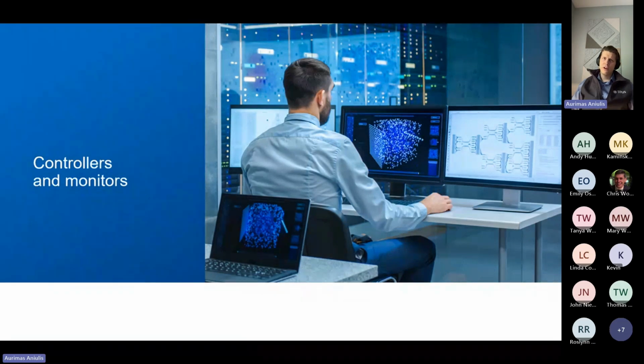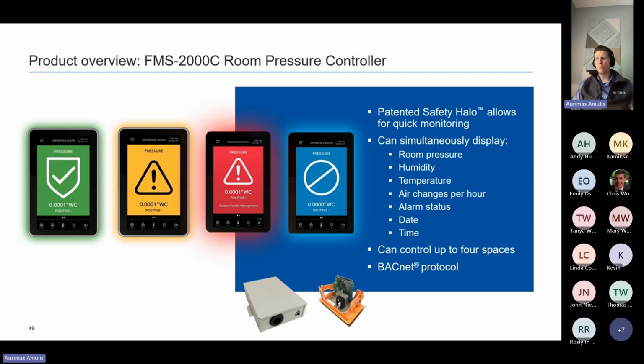So that's it for the air valves. Now we're going to get into controllers and monitors. These are kind of like your brains and your eyes and ears in a space. And the first one is the FMS 2000C room pressure controller. But it's a lot more than just room pressure controls. We call it the critical environment controller because it does humidity, temperature, changes per hour, has multiple alarm conditions and occupancy modes, et cetera, et cetera, et cetera.